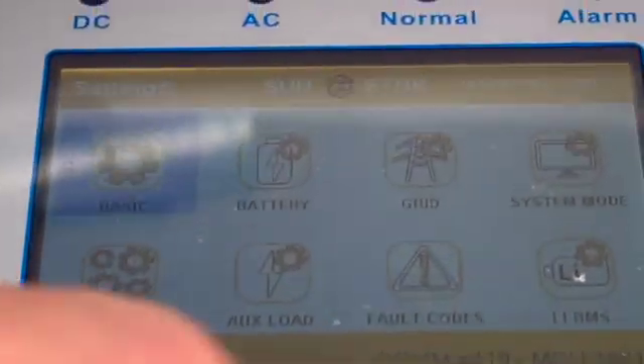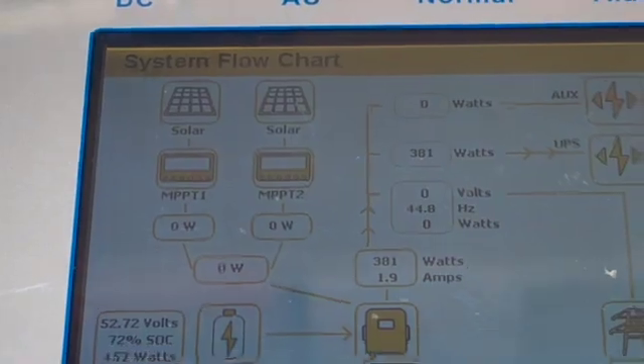One thing to remember: the power coming from the auxiliary port won't always show on the inverter display because of the CT coil. When you look at the mapping of the unit, you can see the auxiliary power going out, but sometimes — especially with a generator — you can't measure the generator power because it's going straight to the common bus bar and back out again. So on our system we measure the time it's running, and that shows on the bar chart.